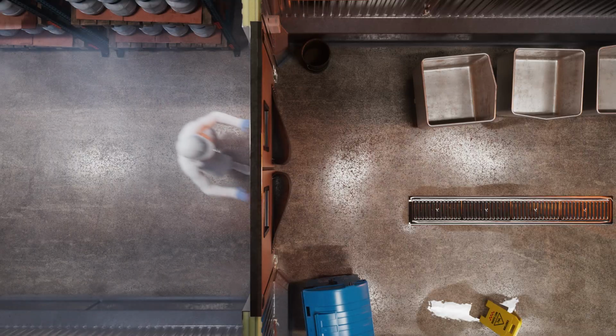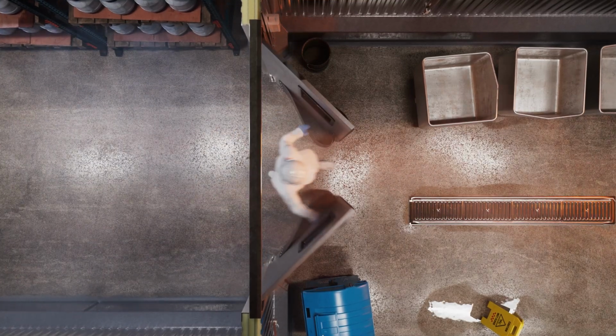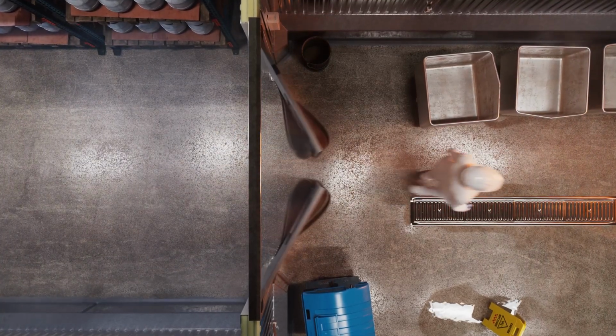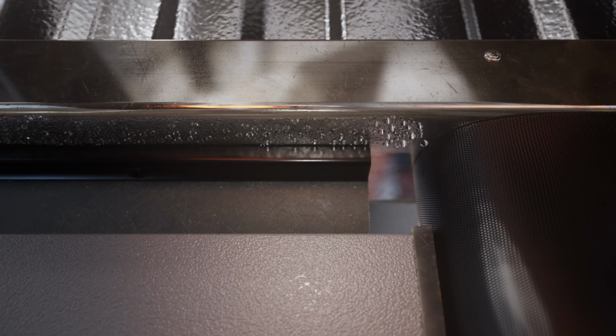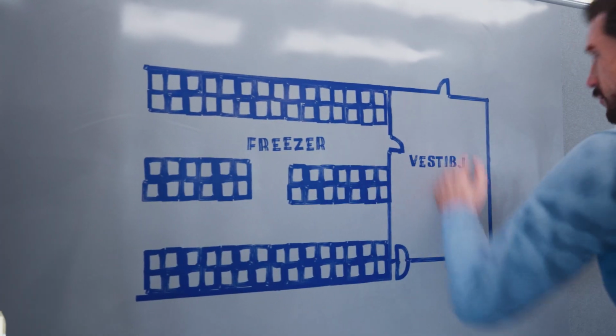Condensation can occur when humid air is drawn into a room through openings, such as doors, and condenses when it reaches the colder room. This condensation can form as moisture on the walls and ceiling or as fog in the room. To solve this, the airflow in the entire facility must be accounted for by investigating the airflow balance.